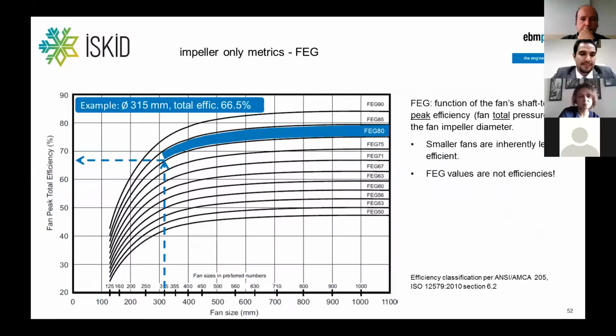So coming to that, metrics. I mentioned wire-to-air data. There is also the so-called FEG, Fan Efficiency Grade. This was developed by AMCA some time ago, but this is based only on the shaft-to-air. So it's only the fan, without the motor, without the drive, and it compares the peak total efficiency related to the fan diameter. So if you are at diameter 315, you need an efficiency of 66.5% to be in the FEG 80 class. But this can be used when considering a fan manufacturer's performance, when the fan manufacturer doesn't offer the motor together with the fan.